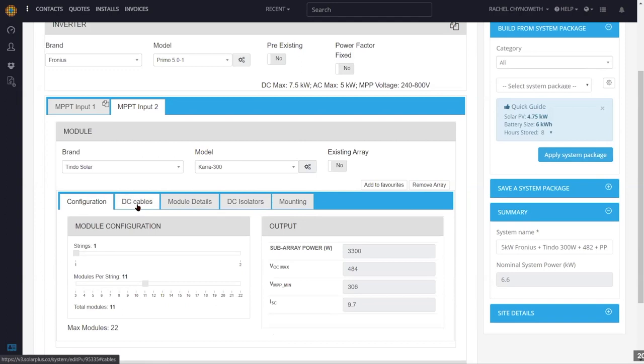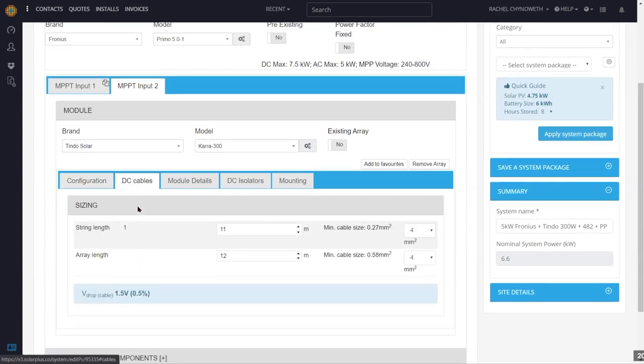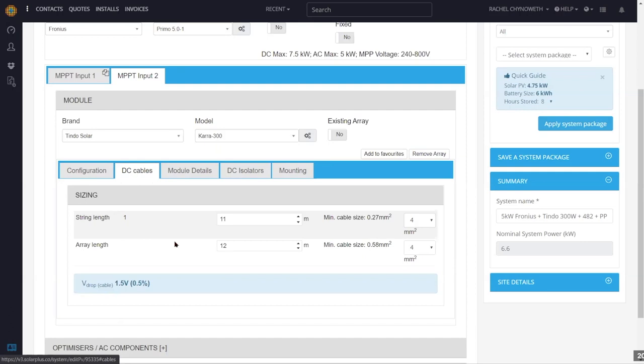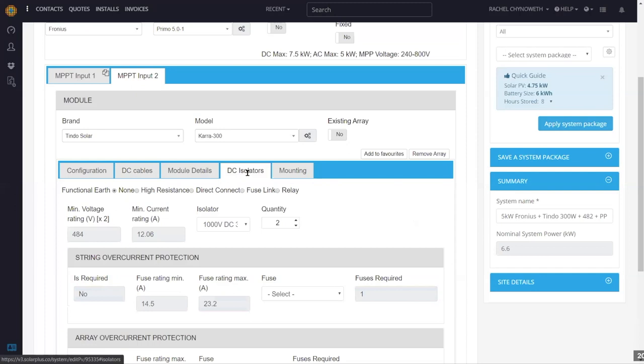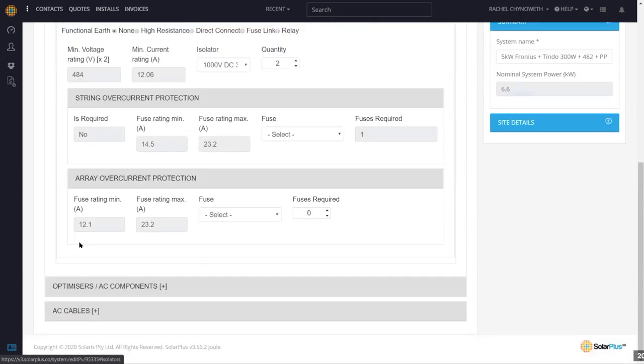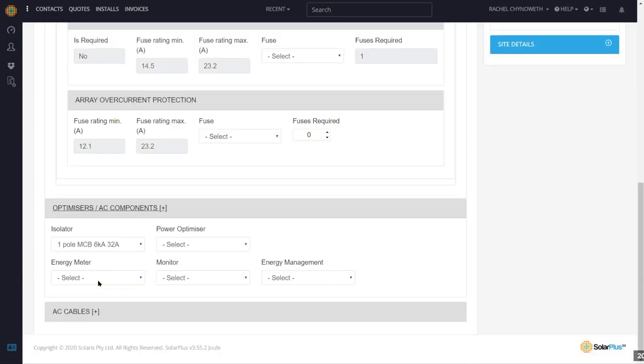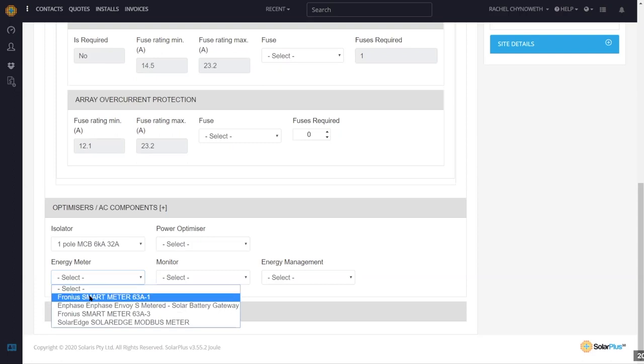We've also got a lot of information in these tabs regarding your DC voltage drop based on your string cable runs and cable size. We can put in our protective devices, mounting, and all of this. I preloaded a system package so you only need to edit what you need — just maybe a couple of fields. If this was just straight solar and inverter to the grid with no batteries, I may add an energy meter for monitoring, and that will also appear on the line diagram.